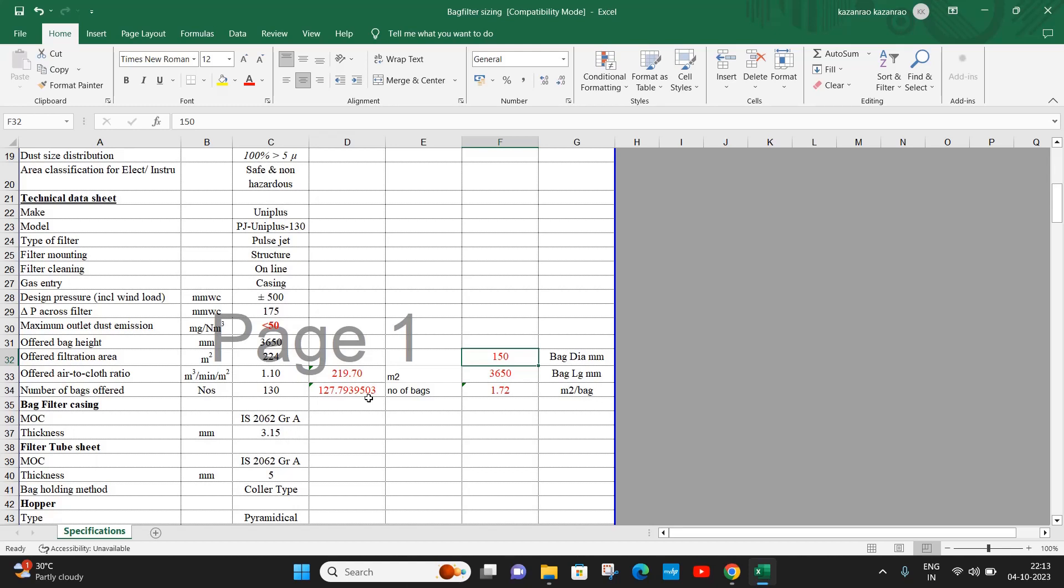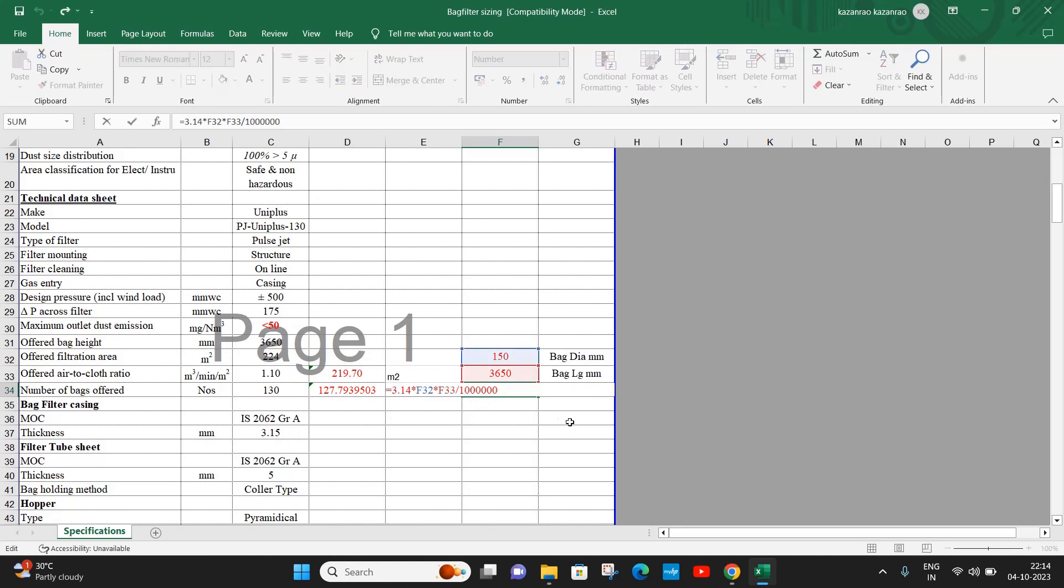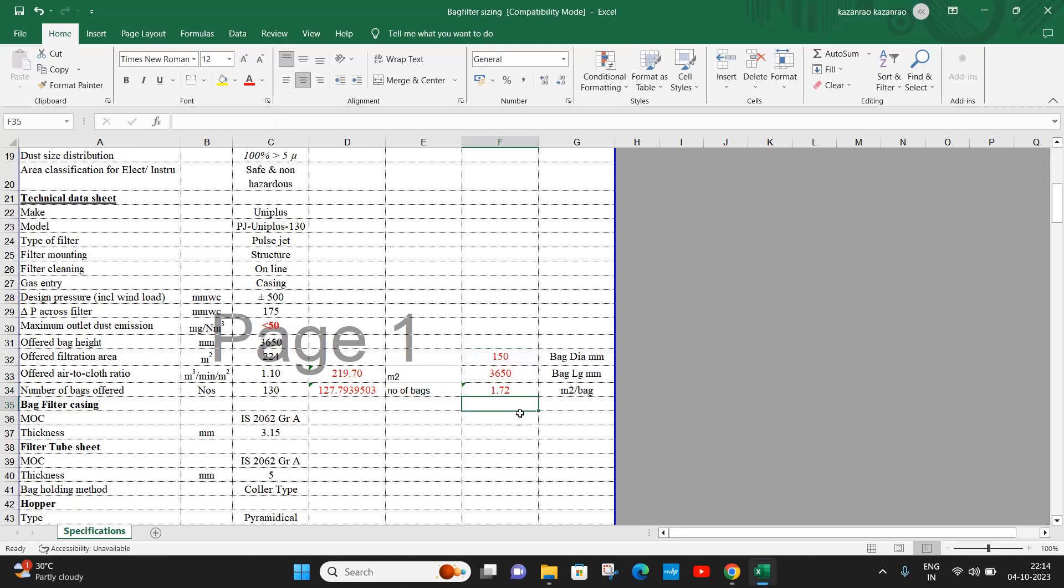Now let us see the size of a regular bag filter. The size of the bag filter is 150mm diameter by 3650mm long. The area, as you know, is pi × d × l surface area, so the surface area for one bag is 1.72.